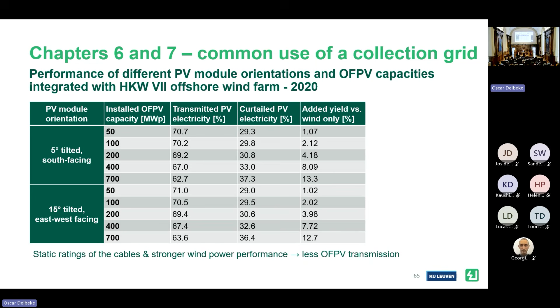First, here we had to use the static ratings of the cable, so we could not use dynamic thermal rating. But also, these modern wind turbines, 15 megawatts, have such good capacity factors, such good performance throughout the year, even in summer, that the gap in the connections that offshore PV could make use of for free becomes much narrower.